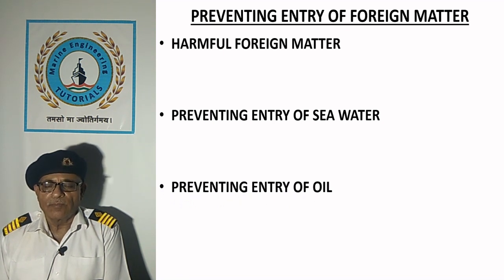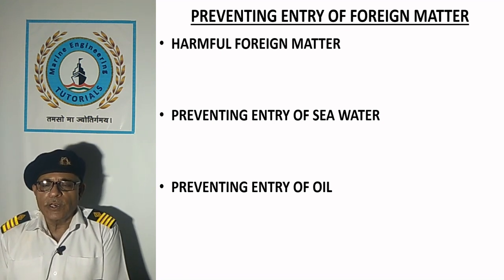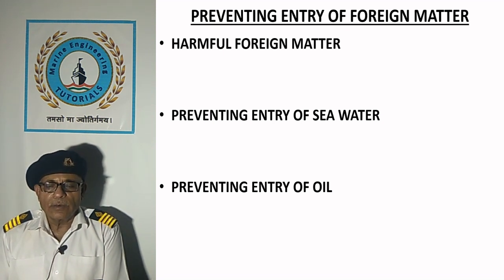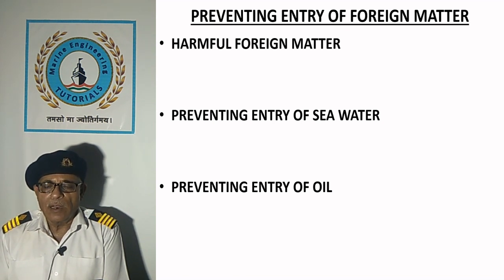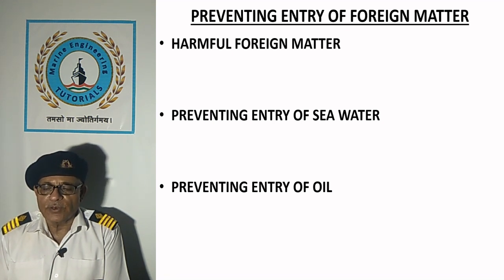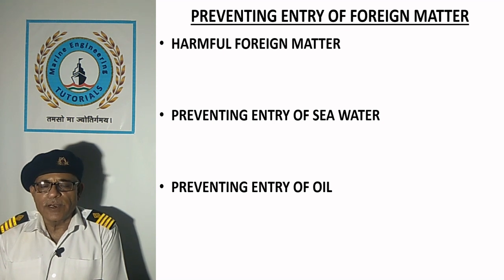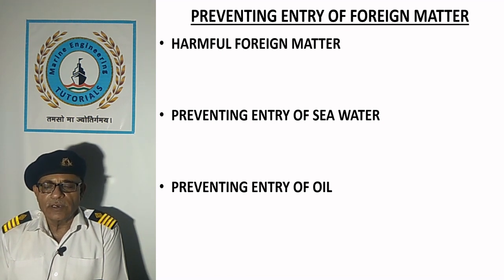Preventing entry of oil: steam is mainly used on motor ships for heating of fuel, lubricating, cargo oil or slops. Leakage of heating coils or tubes can result in entry of oil into the boiler through returning condensate. The arrangement of the cascade tank is such that if oil comes with the returning condensate, oil is easily detected from the observation tank and cannot easily pass to the boiler unless operators completely neglect it. Modern ships are equipped with an alarm if oil is detected in the observation tank.